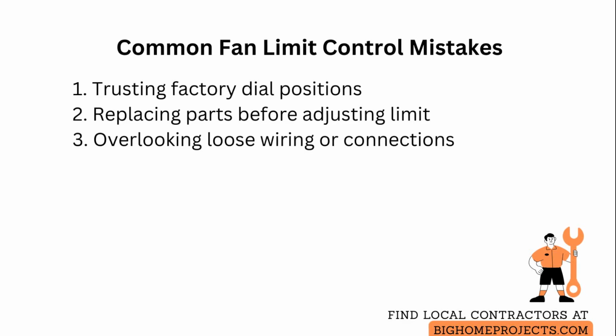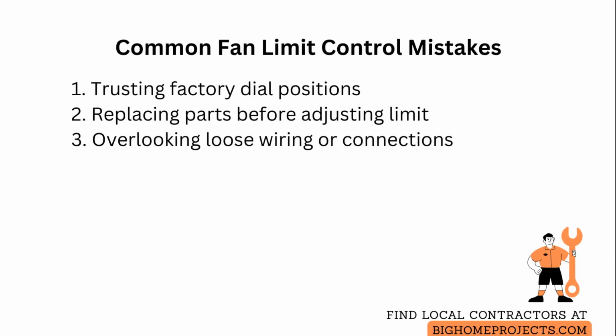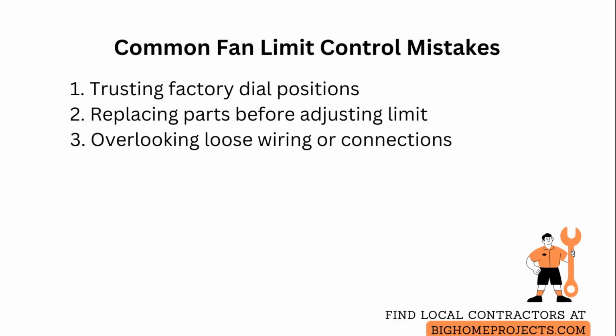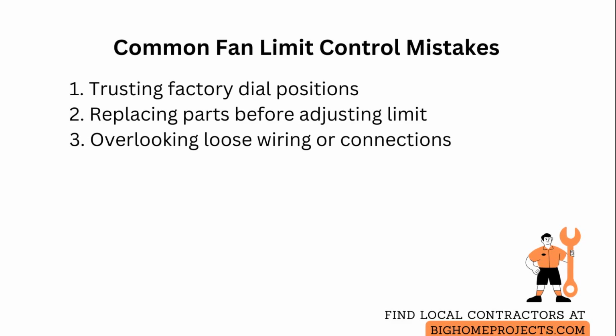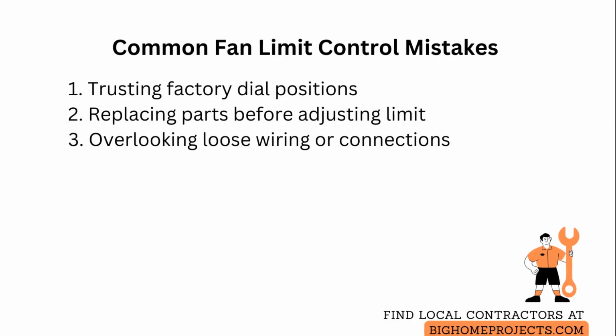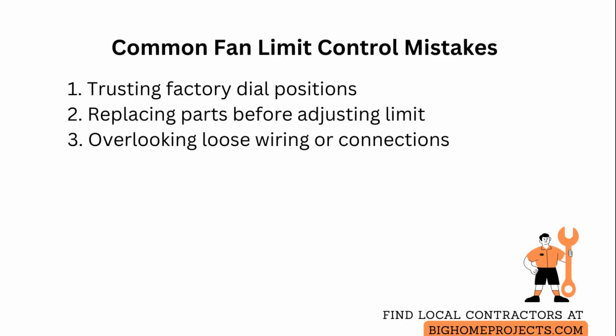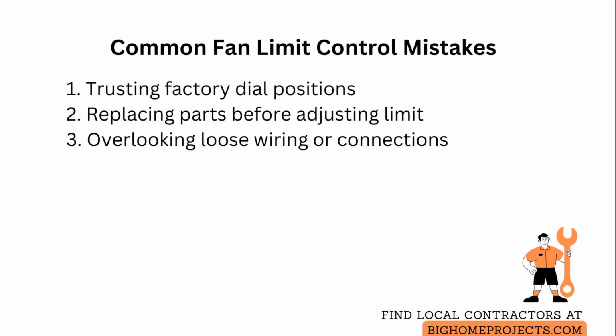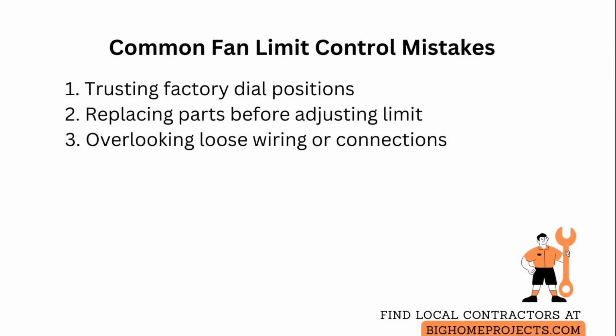Another frequent issue is replacing the thermostat or blower motor first when the limit control is out of calibration. Test and adjust the limit control before replacing expensive components. Finally, people often overlook simple wiring problems or loose connections that mimic device failure. Inspect and tighten the terminal screws, and look for burned or brittle insulation and replace the control if wiring damage is found.